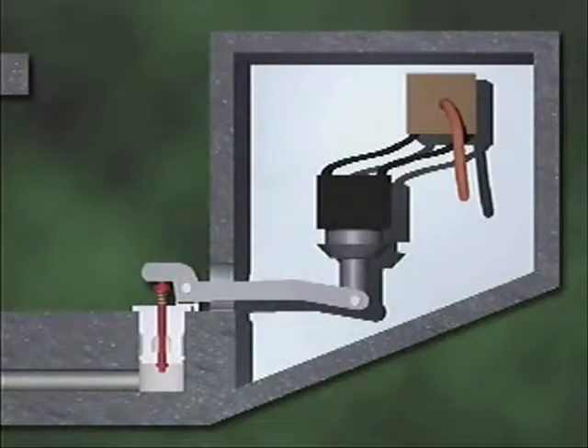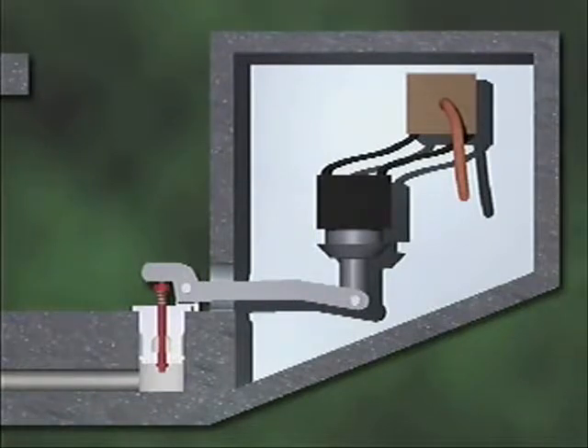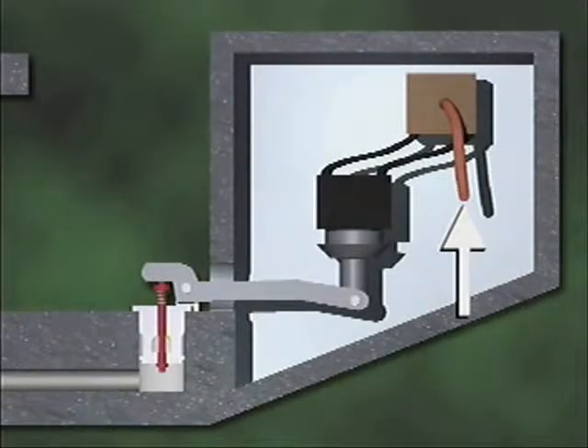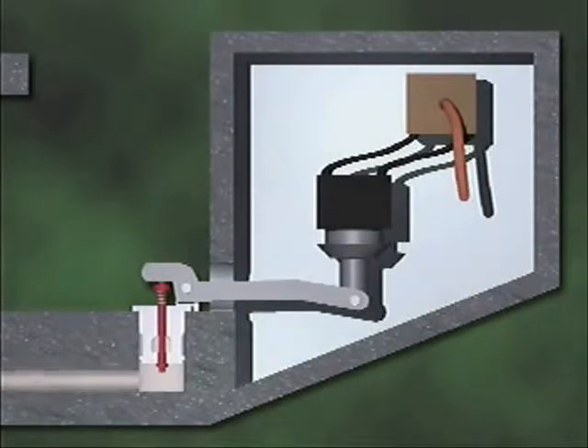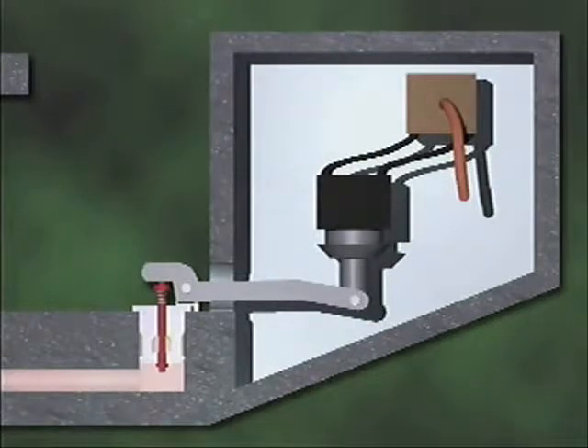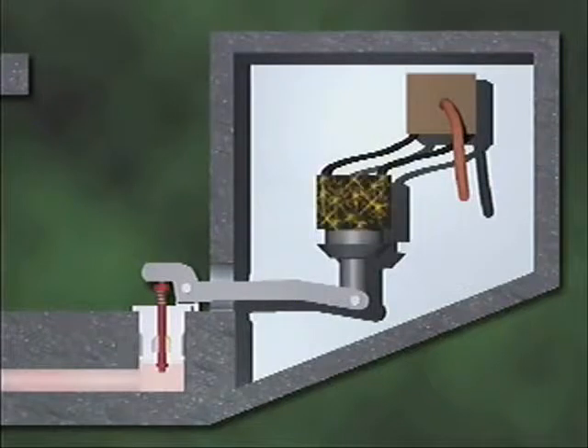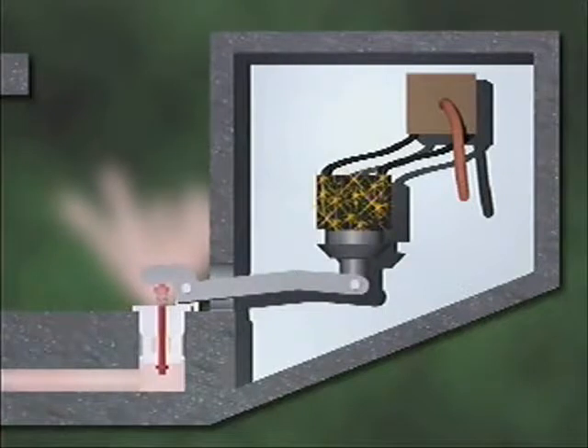The pilot device initiates the valve's opening and is set to open at a predetermined pressure. A pressure-sensing tube in the pilot device detects increases in system pressure, and when system pressure reaches the predetermined level, the pressure-sensing tube activates an electrical relay. The electrical relay closes an electrical circuit and energizes a solenoid, which then lifts a pilot valve, relieving the excess pressure.